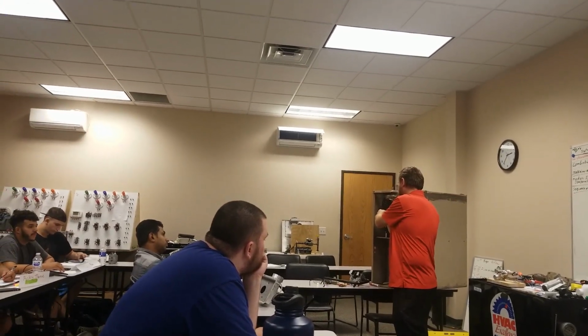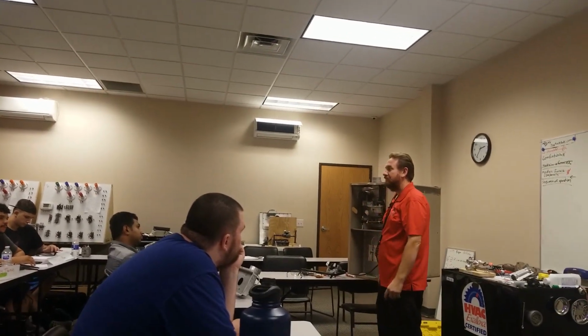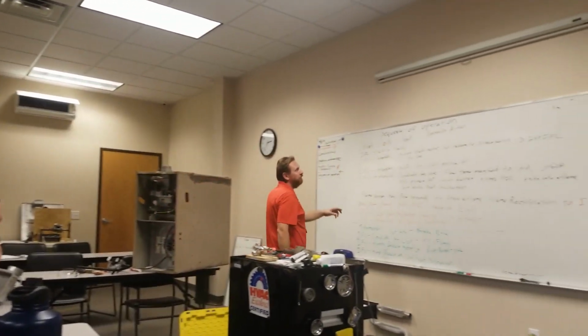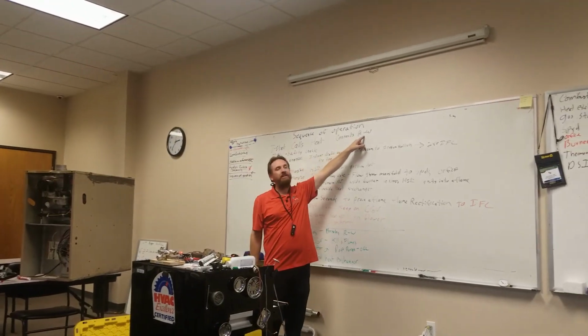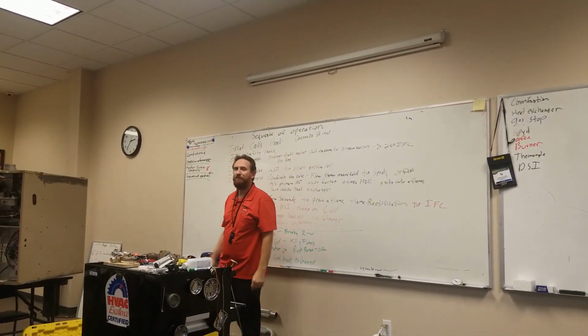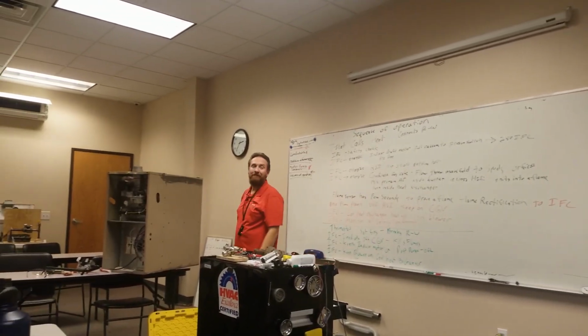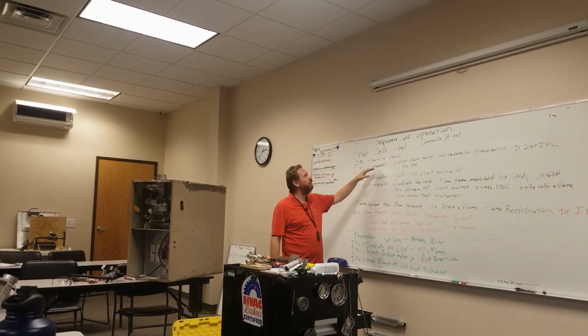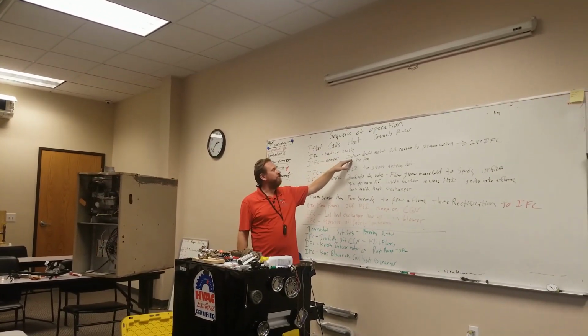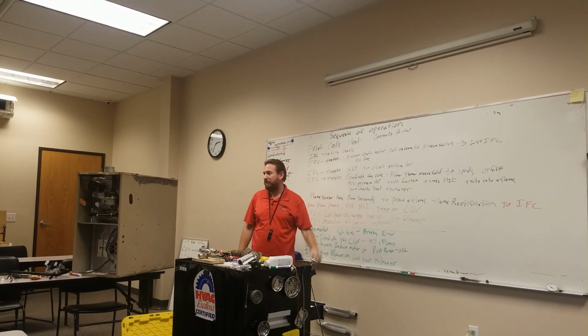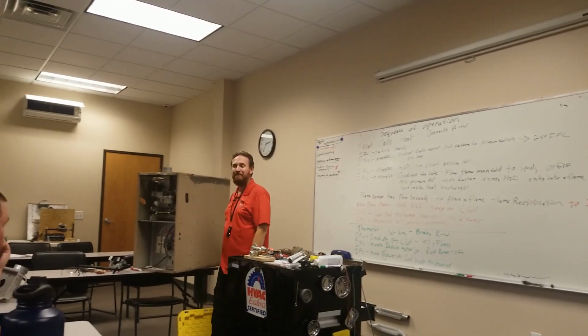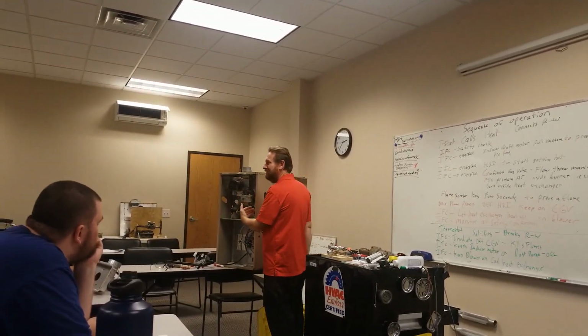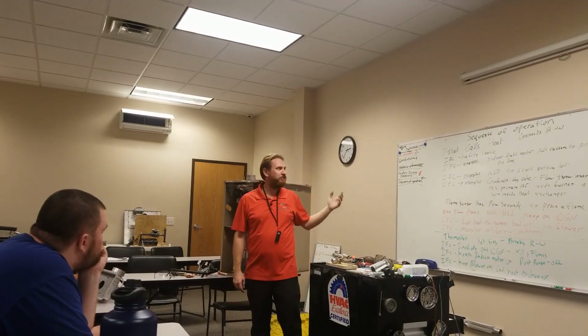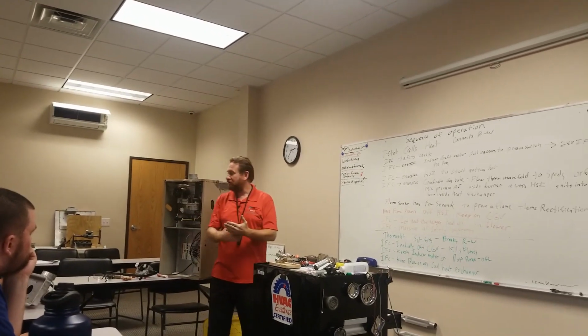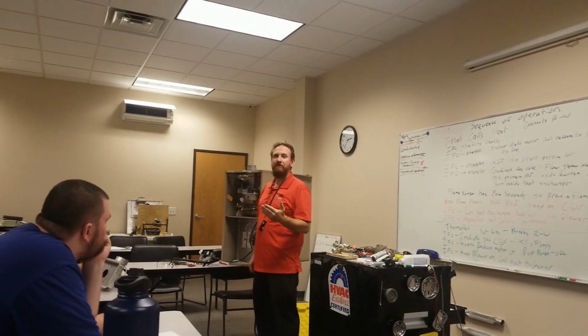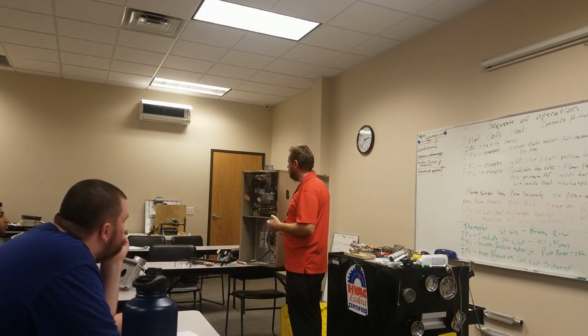Scenario number 2. I'm not getting voltage here. How about I check between R and W to see if I'm getting the signal to the control board? And then maybe I should check to see if there's any kind of a code, because it's going to do a safety check. Maybe there's a safety issue. It's not letting anything happen. See those steps? Yeah. Now, you're not going to have these memorized in 2 days, but you should have this paper digitally with you so that you can see what's going on. This is your key to diagnosing the unit.